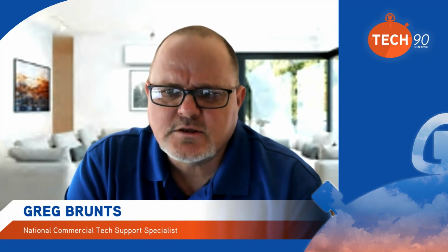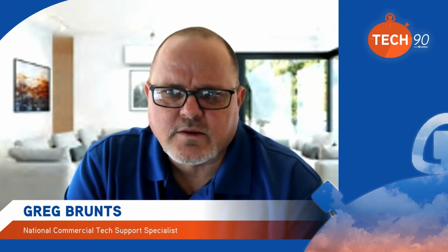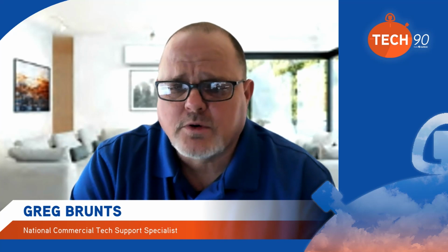What about you, Greg? Well, I think those are interesting points, but another big thing to think about here is MultiPRO. I think there are a lot of people who would be seriously interested in MultiPRO because of its heating capabilities. But we were limited in the market in that there are a lot of existing homes that already have gas furnaces installed in them. And in order to do a MultiPRO up until now, you would have to remove that whole furnace and put in an air handler, effectively decommissioning the gas lines that went to that furnace. This gives us the ability to let them keep that gas furnace and the fuel runs they already had, and be able to add MultiPRO systems into it.